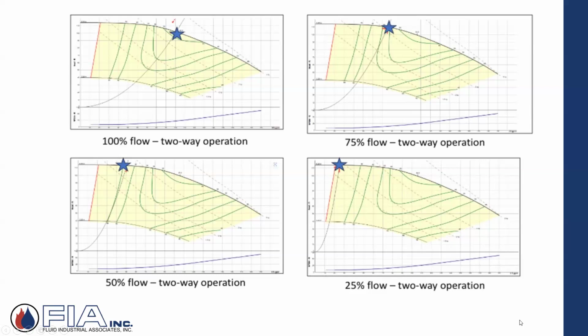And it's just continually changing. But it would constantly what? It's constantly moving back to the left. It's developing higher head on that constant speed as the flow is being reduced. Why is it being reduced? Because the valves are closing, because the set point's being satisfied.